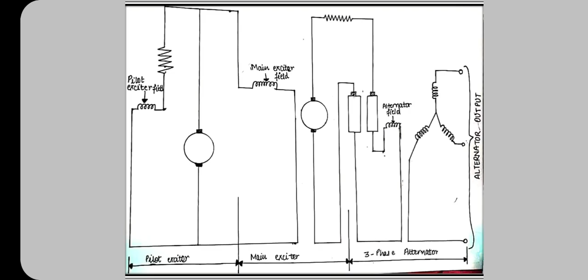The supply from the pilot exciter is given to the field of the main exciter, and the supply from the main exciter, which is a separately excited DC generator, is directly fed to the field winding of the alternator through slip rings and brushes. But this conventional method of excitation suffers from cooling and maintenance problems due to the association of slip rings and brushes. So other methods of excitation were developed.